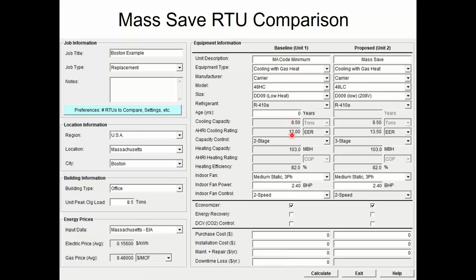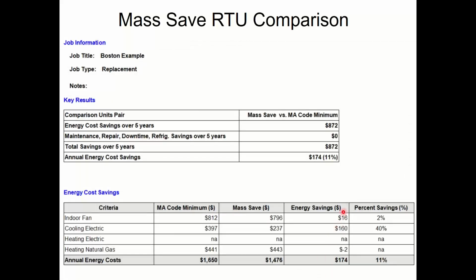So I plugged in that legal minimum option. Exact same size of units, exact same size of heating in the units, exact same horsepower of the fans. They're both 2-speed fans because that's code required now. They both have economizers. All I did was get slightly more efficient on the cooling side. And that, in this case, for me, is 11% improvement. And that's $174. It's not that exciting, but it's nice, right?